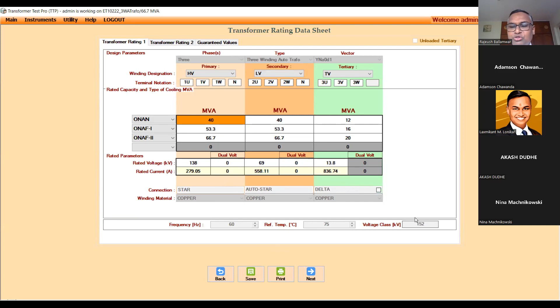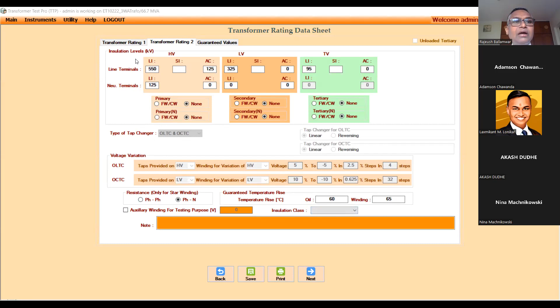Here you are in a position to see the insulation levels for lightning impulse as well as the alternating currents for line terminals as well as the neutral terminals. Next you can go for the type of tap changer. You can go for OLTC, OCTC, whatever it is. And then you have the voltage variation for OLTC, OCTC. That means both the windings. You can set it the way you want it. You can go for how you're going to have the measurement of the resistances and all that. Those settings are there. But as a default, you can just go ahead. Then the guaranteed temperature rise for oil and winding is mentioned over here. And that completes transformer rating 1, rating 2.